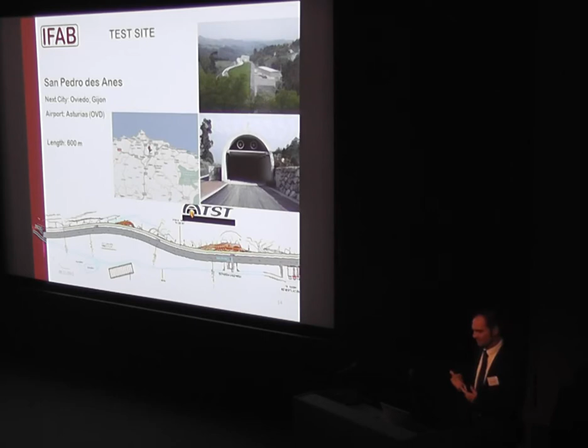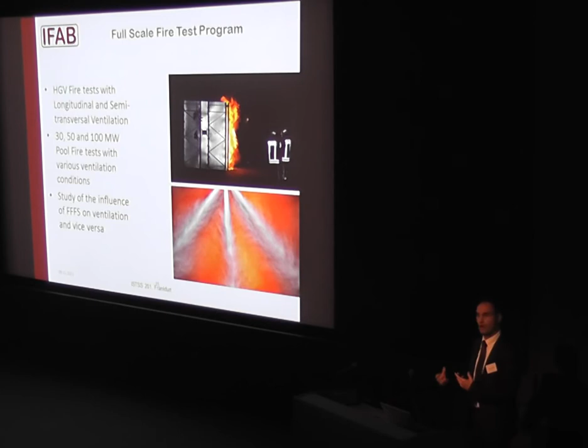And we did some truck fire testing with longitudinal and semi-transversal ventilation. So we had a suspended ceiling with some smoke dampers and a smoke extraction system in there. We did also some pool fires, 30, 50 to 60 megawatt and 100 megawatt pool fires, and I can tell you that's really a challenge to do pool fires with this size. And of course, one of the major aims of this research or test program was to study the influence of a firefighting system together with the ventilation. So what is happening there? What are the effects on the ventilation, but also on the firefighting system?